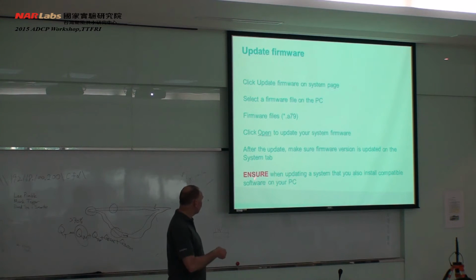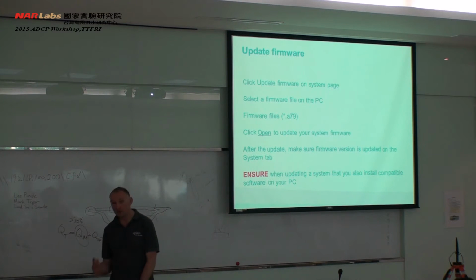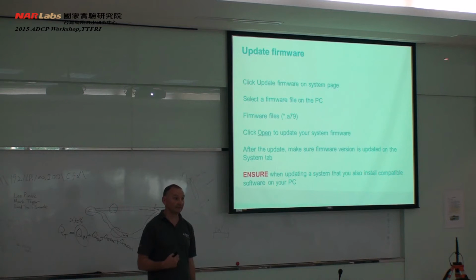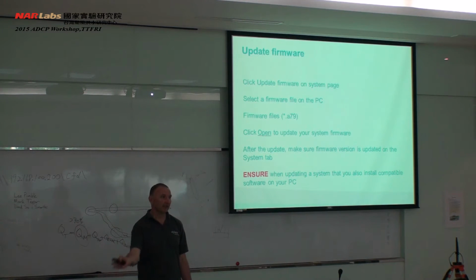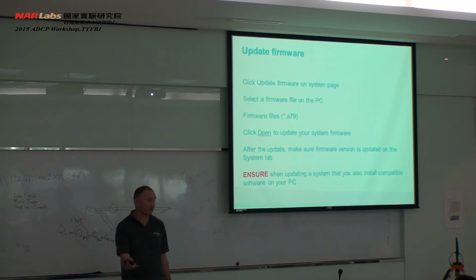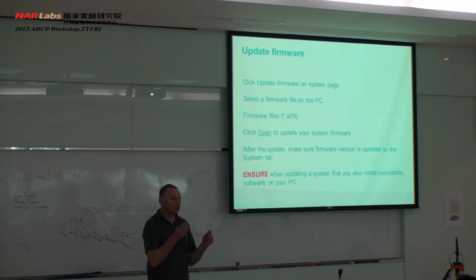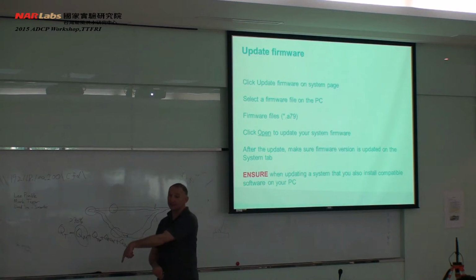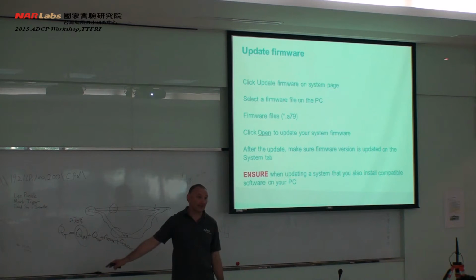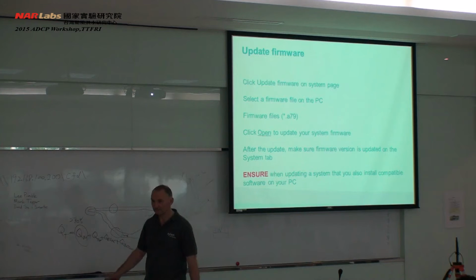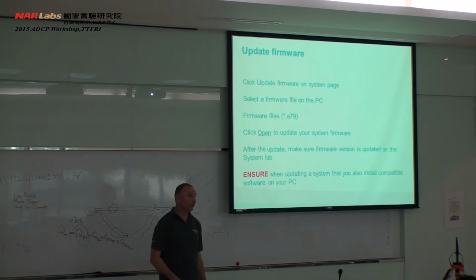A really important thing though is to ensure that when you put new firmware on, you use new software too. In many instances, people will update the firmware on the instrument and then think that they can use the old software. And then they phone in and say, oh, the instrument's not working. And similarly, people download new software from the website and don't put the new firmware onto the instrument. So you should run them compatibly. In some situations, new software will work with old firmware, as you would expect. But with this instrument with the new compass in it, if you've got the G3 compass, you have to go to the 3.8 software. The 3.5 software wouldn't work with that, whereas the 3.8 software would work with the older compass.